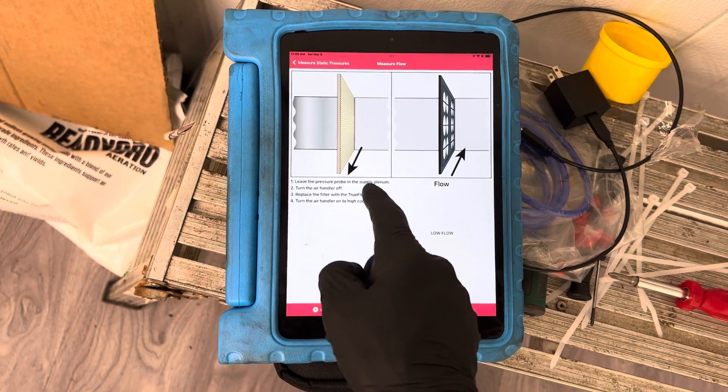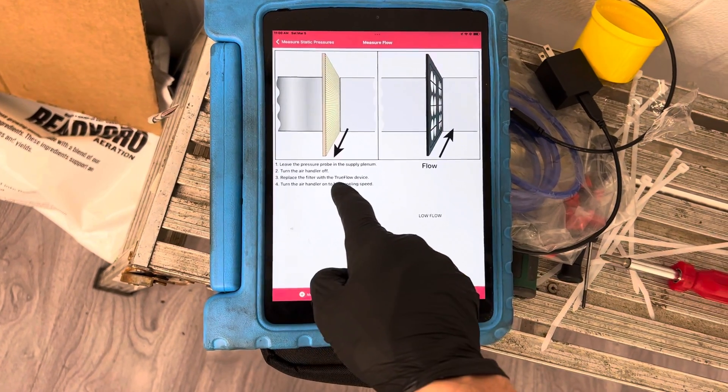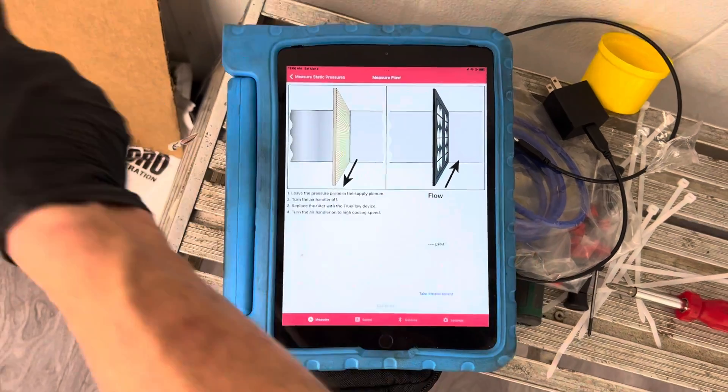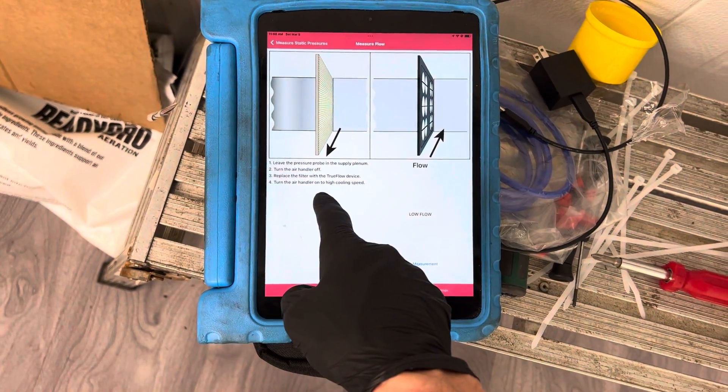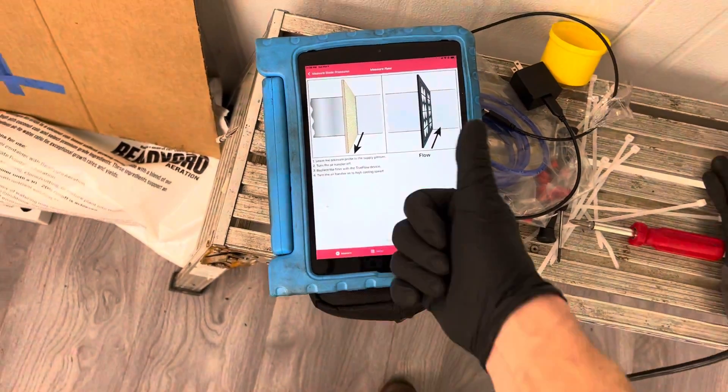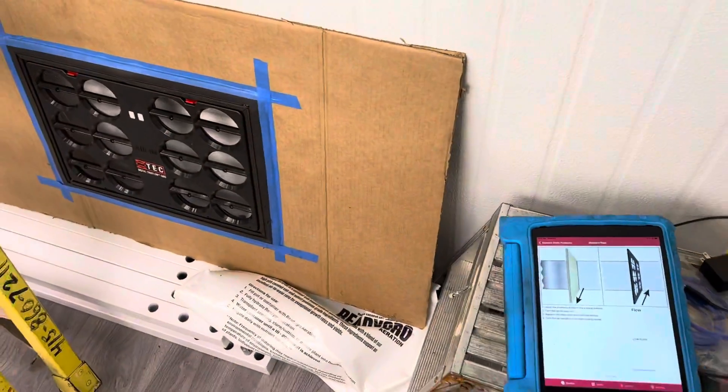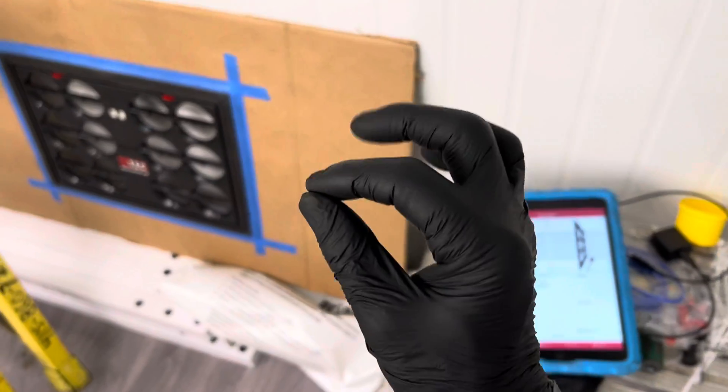Now it says leave in the pressure probe, turn the air handler off, replace the filter with the true flow grid device—that's that device right there—and turn the air handler on high cooling speed. Real simple, it's not rocket science. Anybody can do this. It's so much better than traversing with the fans or doing a pitot tube traverse.